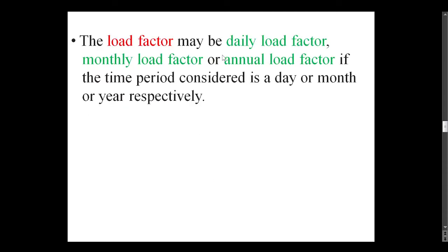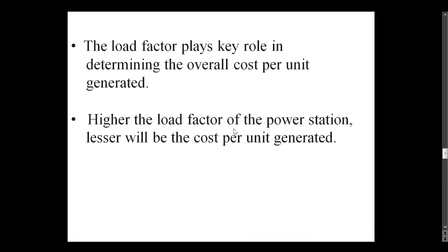The load factor may be daily load factor, monthly load factor or annual load factor if the time period considered is a day or month or year respectively. Load factor is always less than 1 because average load is smaller than the maximum demand. The load factor plays a key role in determining the overall cost per unit generated. The higher the load factor of the power station, the lesser will be the cost per unit generated.